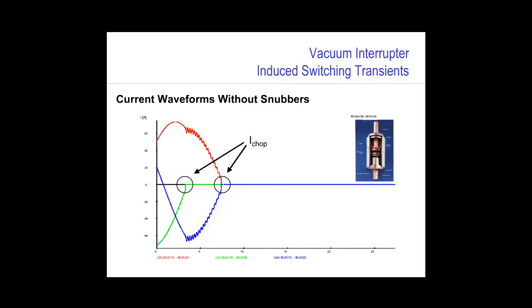So after you ask the interrupter to open, because it interrupts in vacuum, as current drives towards the chop current value, let's say 5 amps, it will go from 5 amperes to 0 instantaneously. You can see from the 3-phase current trace on this slide the impact of chop current. As the current drives towards 0, when it gets to the chop value, let's say 5 amperes, it instantaneously goes to 0 amperes.